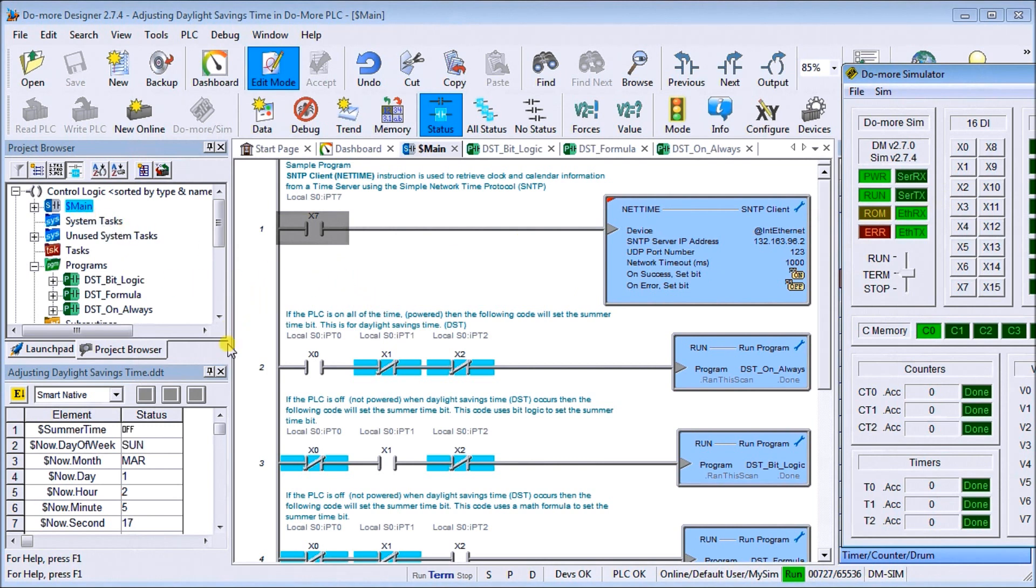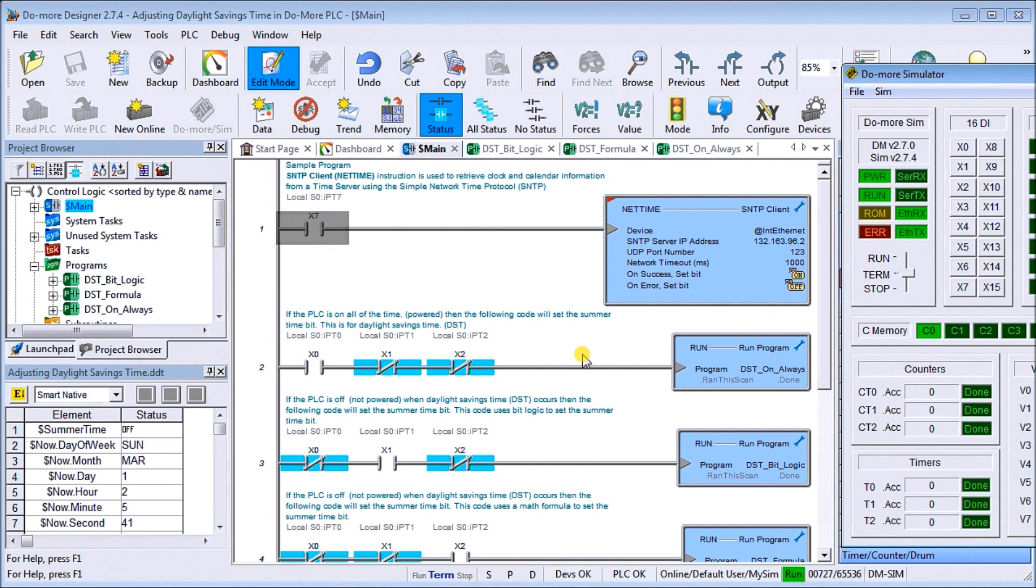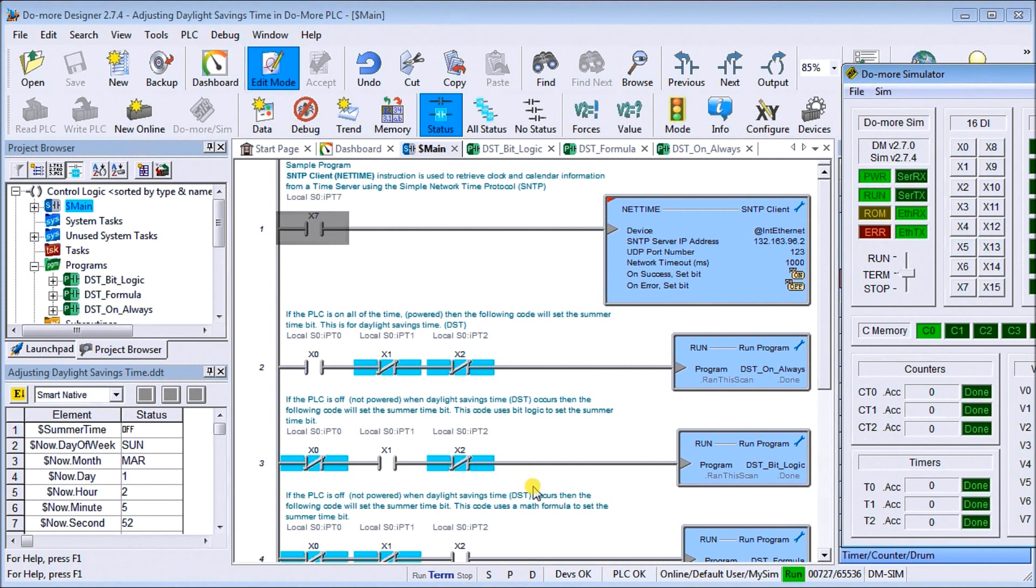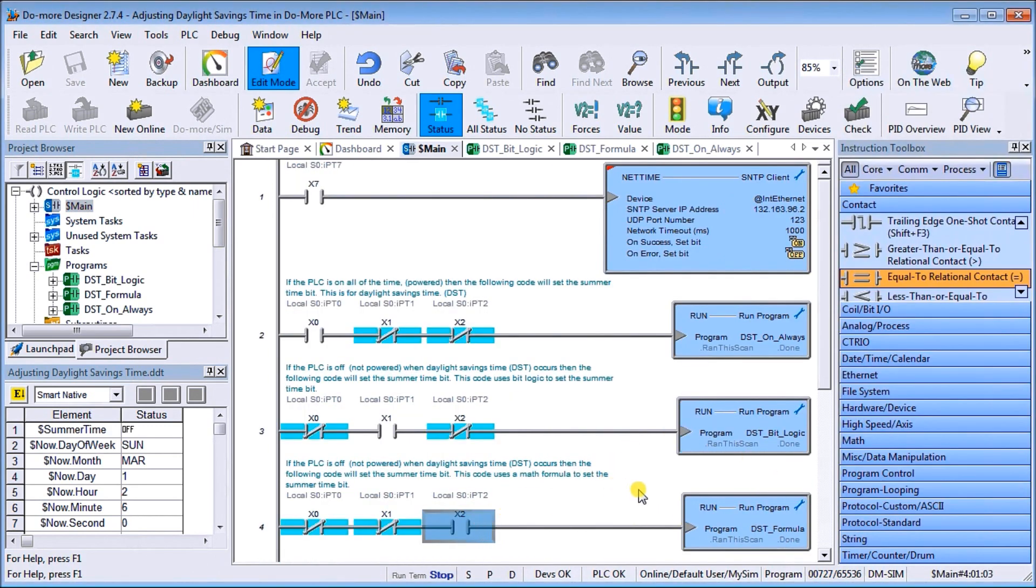Let's take a look at what we have here. This first program here is running when the PLC is always on and we're always monitoring that summertime bit. Then what we've done is we said, well if the PLC turns off and on all the time and we can't guarantee that it's on when daylight savings time either goes ahead or falls back, then what we want to do is check for that. There's two different methods that I've placed in the sample program. The first one is using bit logic and it basically monitors all the time and sets that bit, or there's a formula that was created and that formula will actually then set the daylight savings time summertime bit.